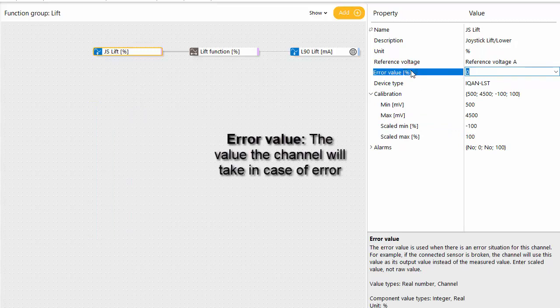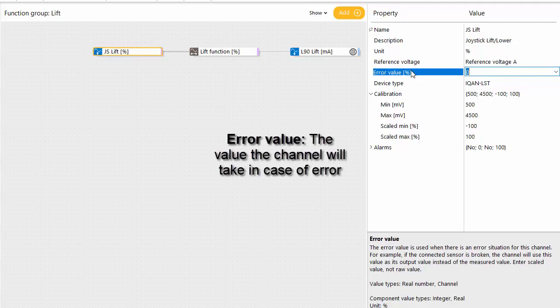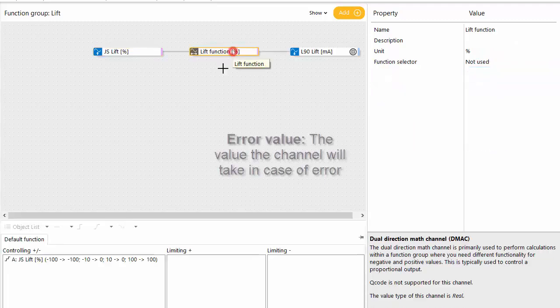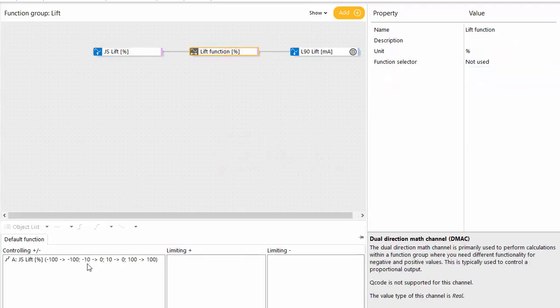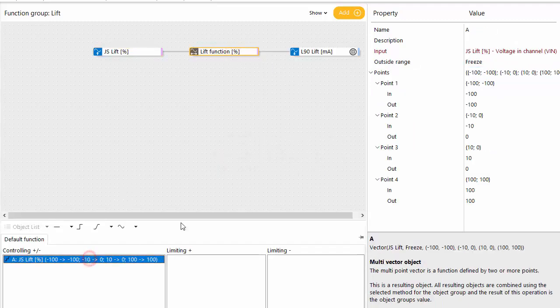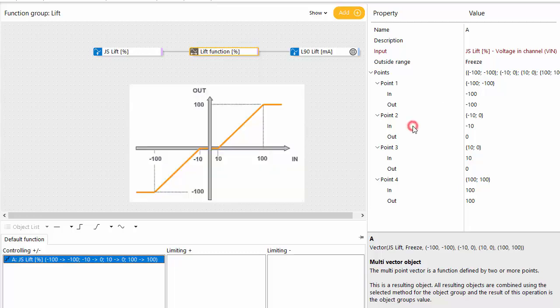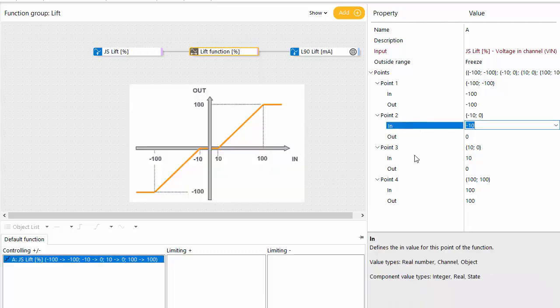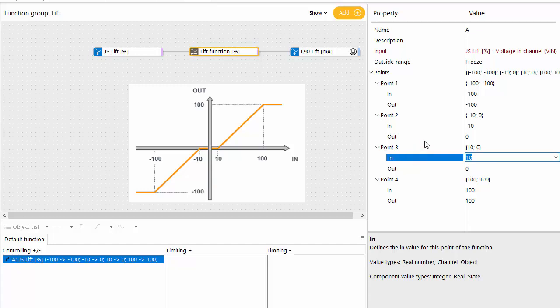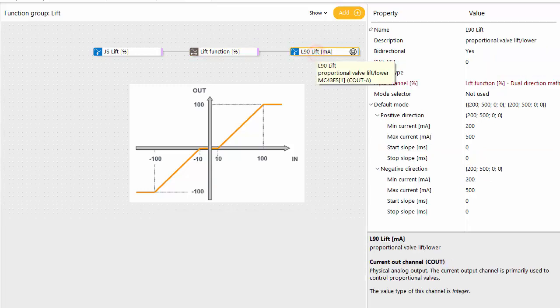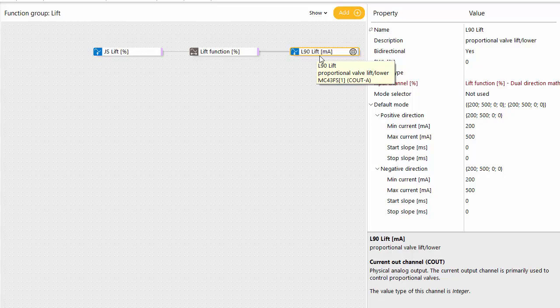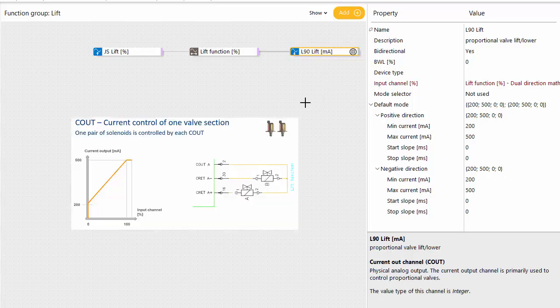So zero is a safe error value in this application corresponding to the same position as we have when the operator lets go of the lever. So that's from the dead band here. Minus 10 to plus 10 gives the function the value zero, and the value zero when that's fed into the current output deactivates the output.